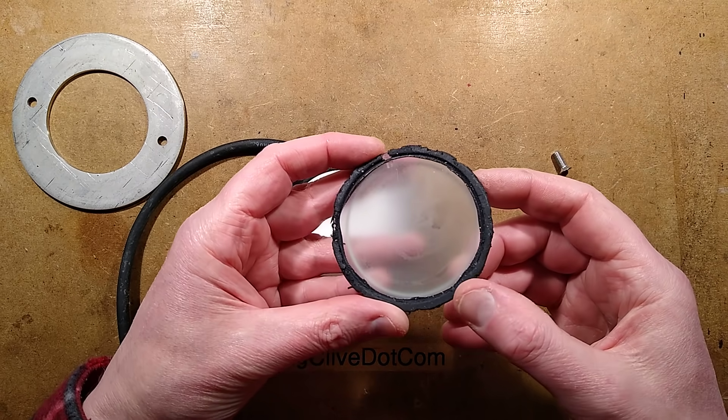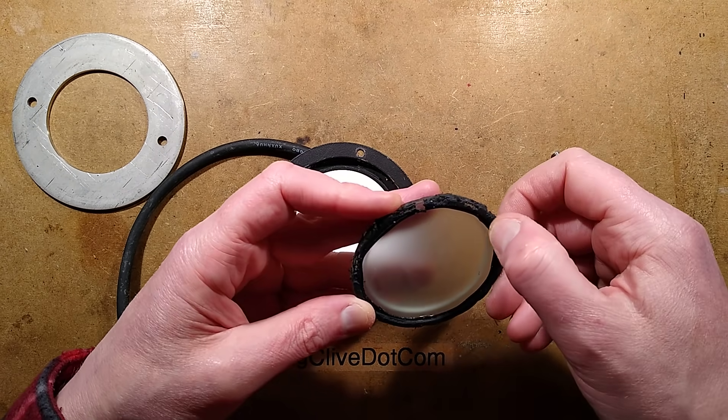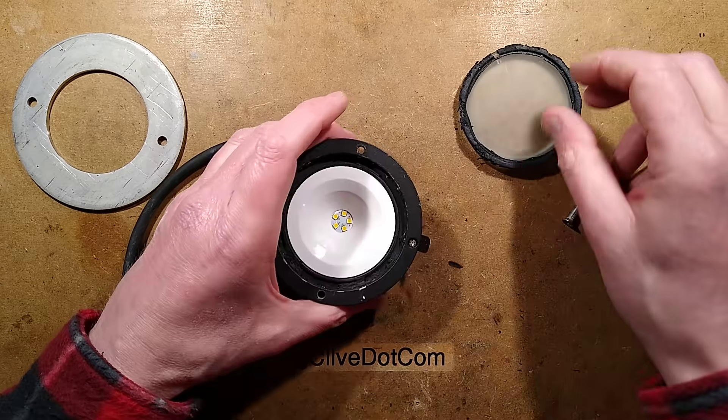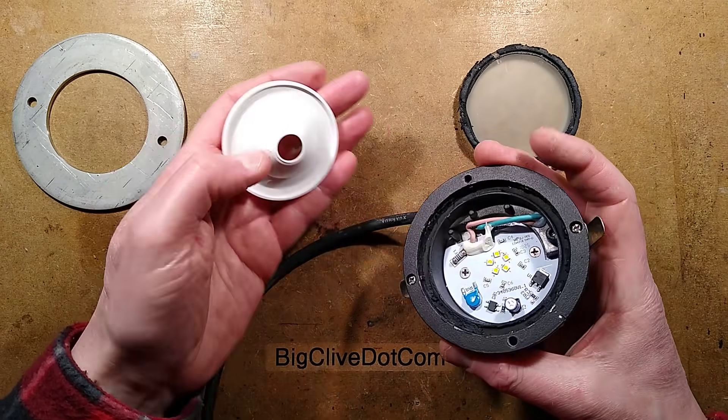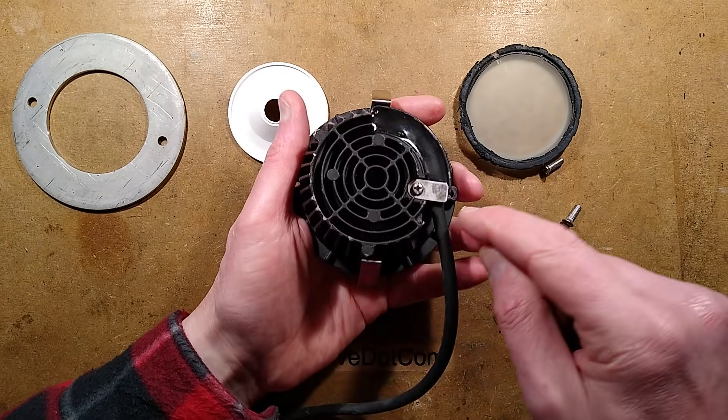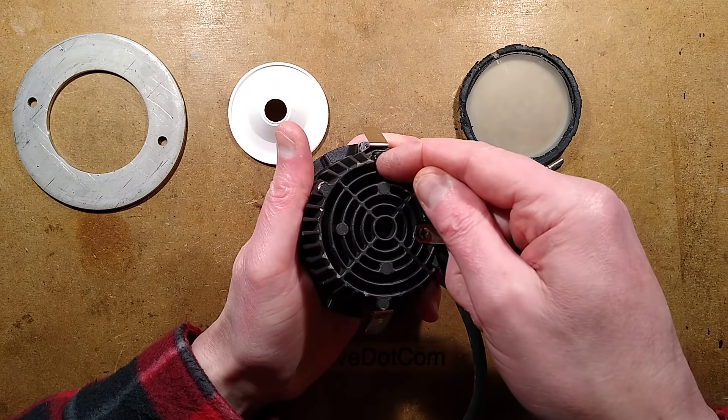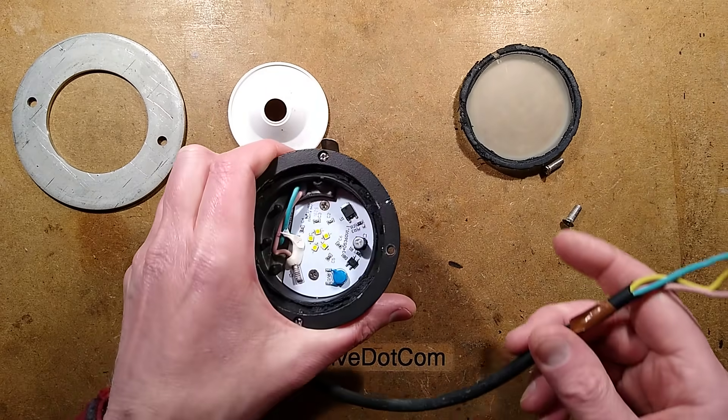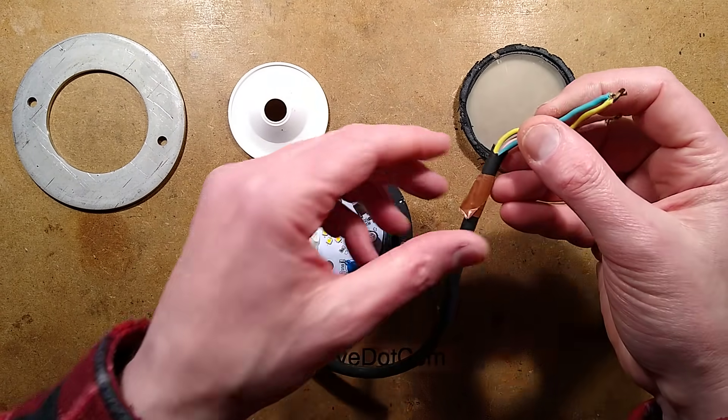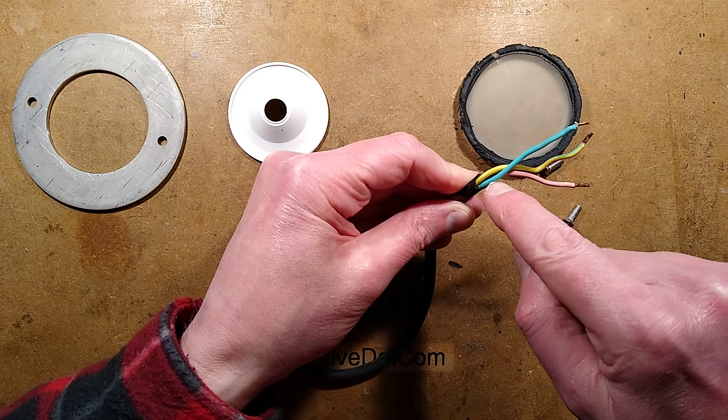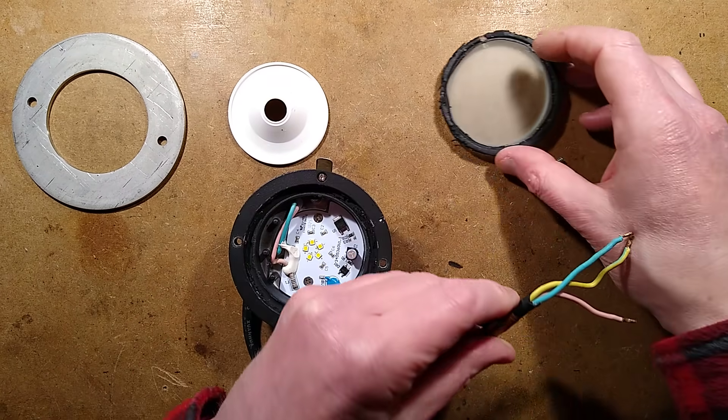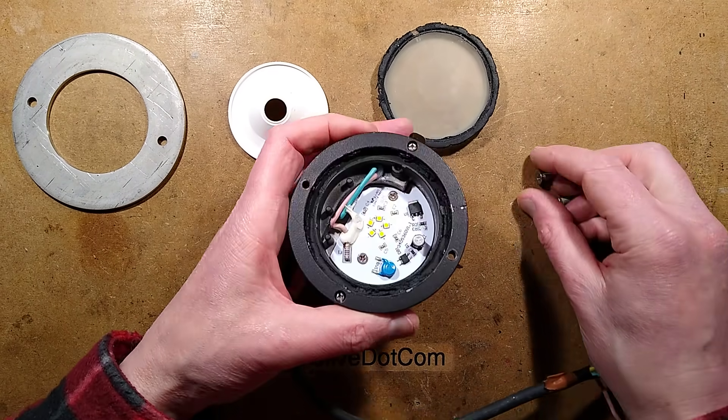So this has been filled round with rubber. And I did notice that the back, the cable here, has a little clamp but it's all been potted with resin. So they've gone to effort to try and avoid the situation that underground lights, water can actually travel up inside the cable. That's something you should consider if you're ever doing outside stuff.